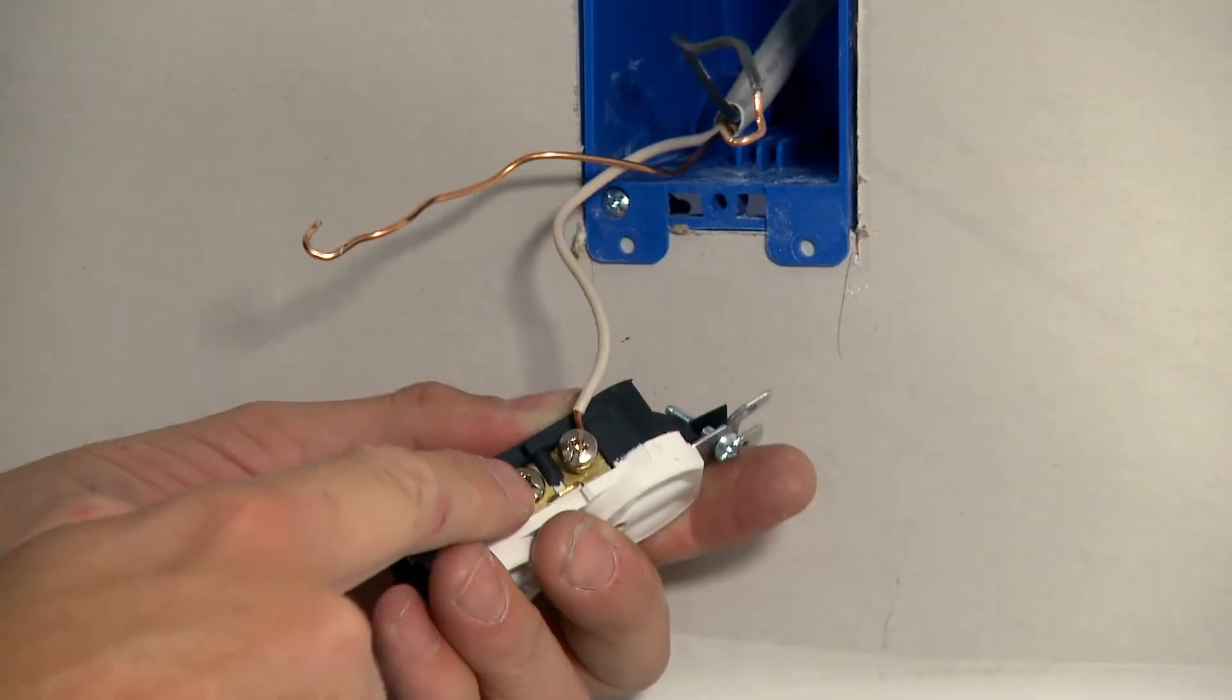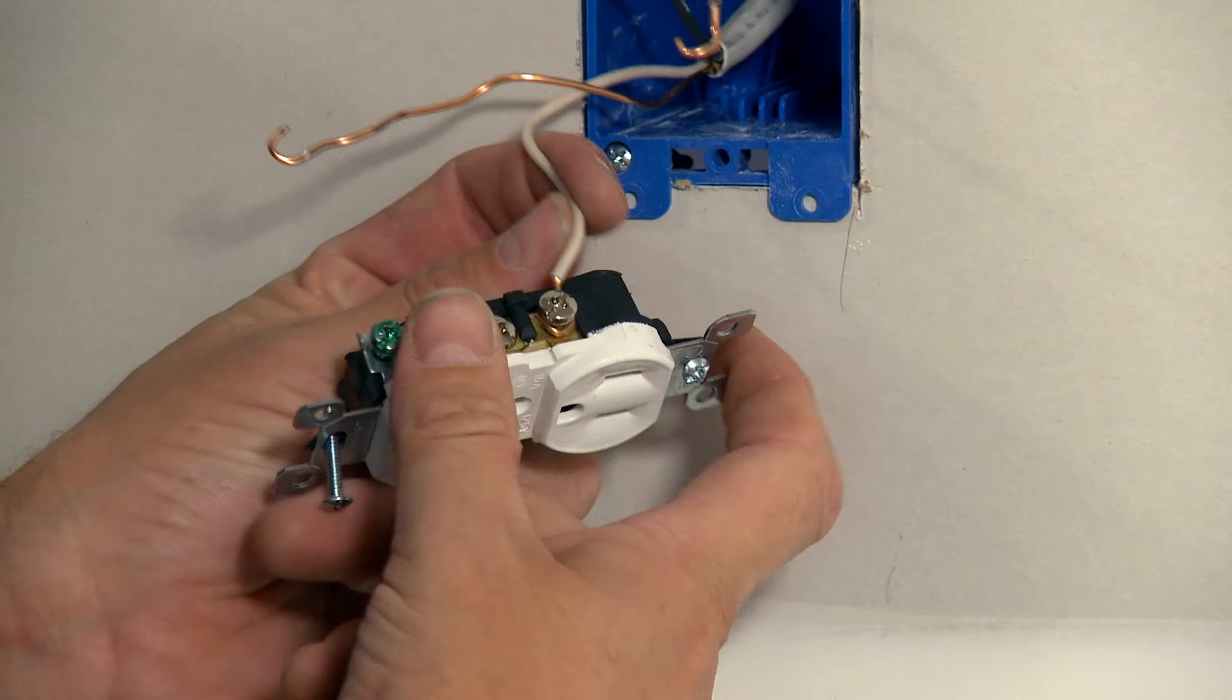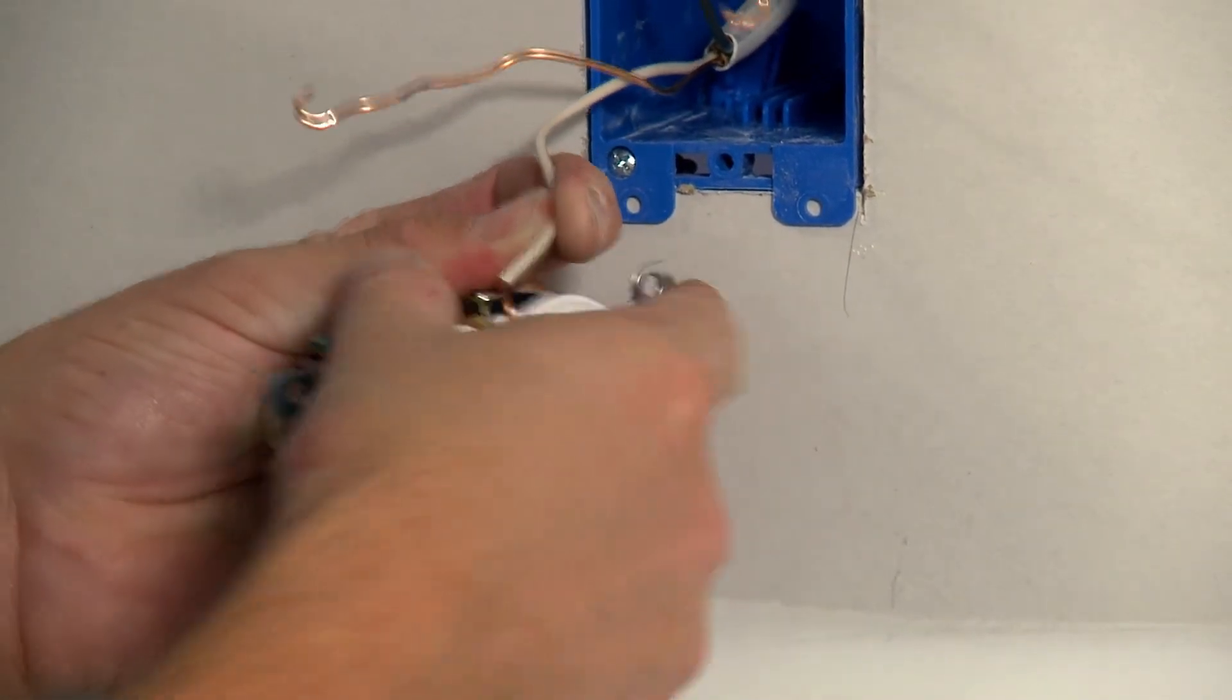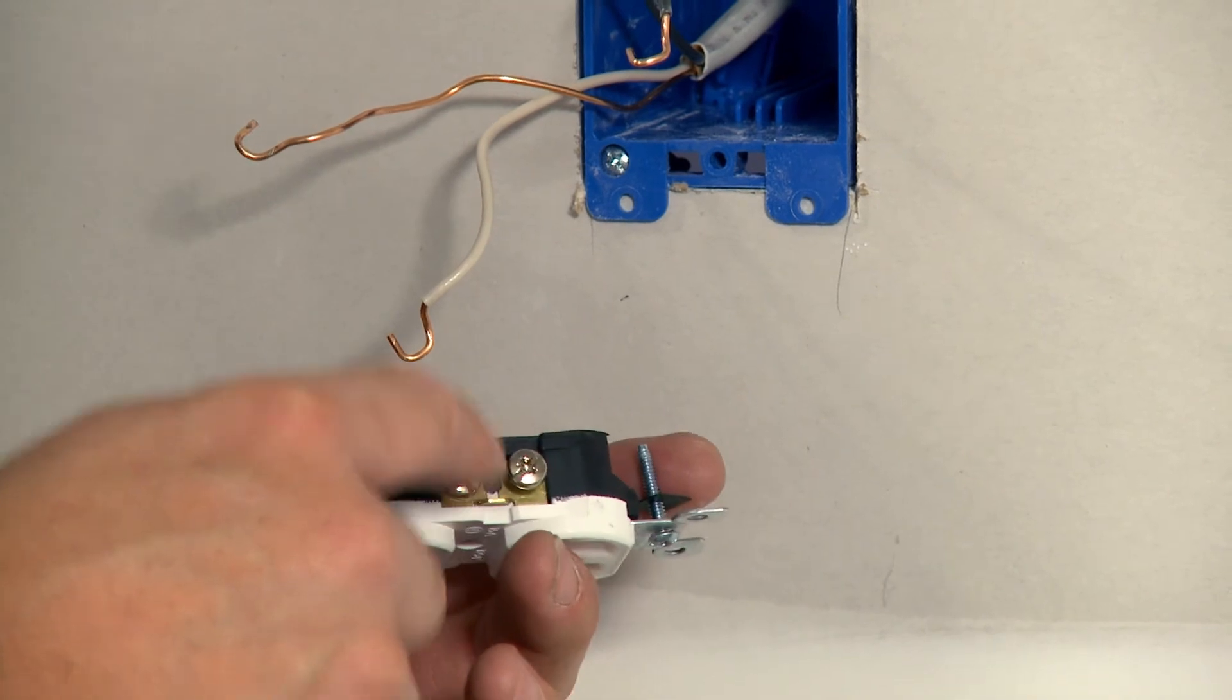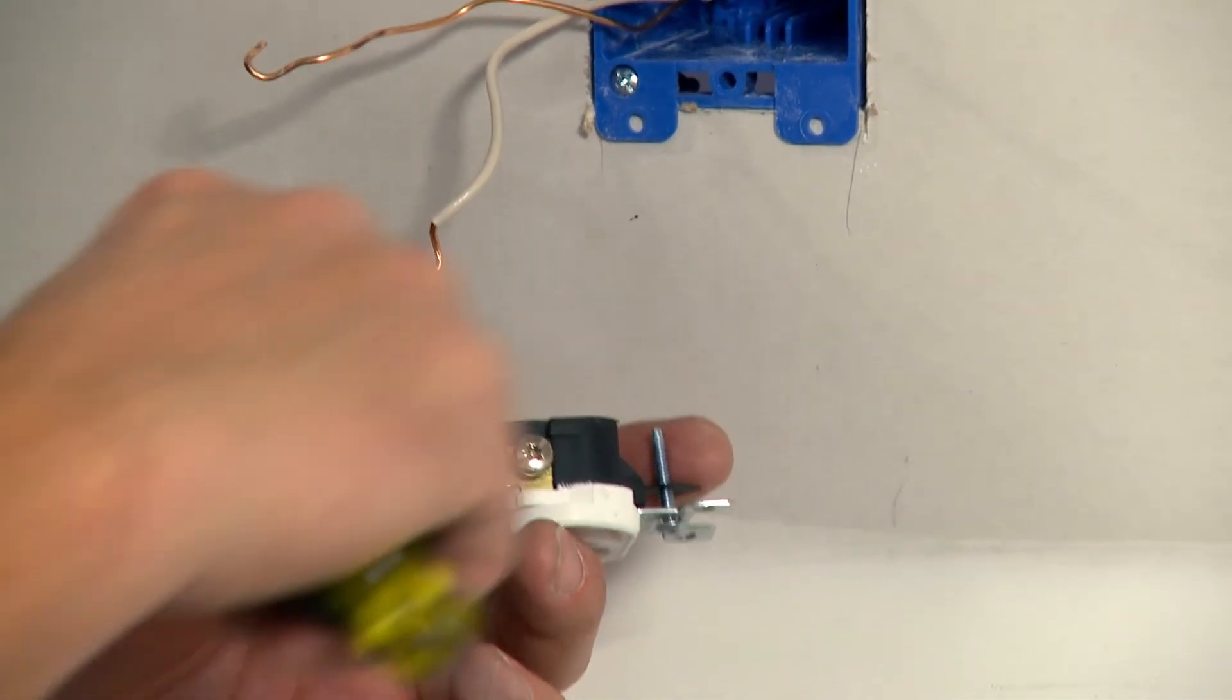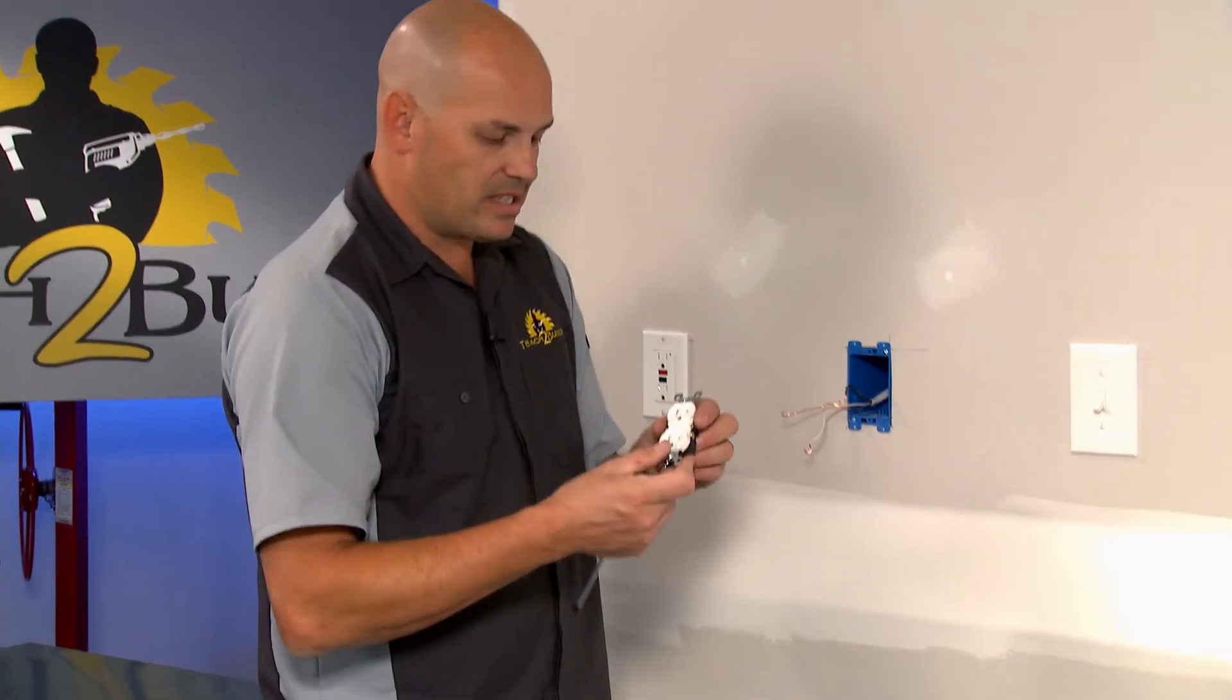Now, you'll notice these were installed properly. The wire wraps clockwise around that. That way, as the screw tightens, it actually grabs a hold of the wire and helps hold it in place. If it was wrapped counterclockwise, as you turn the screw, it would try and push the wire back out that side.